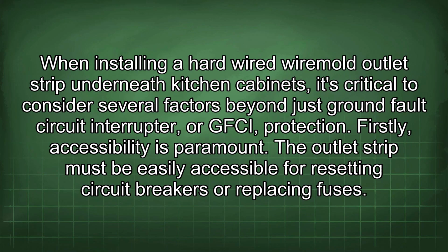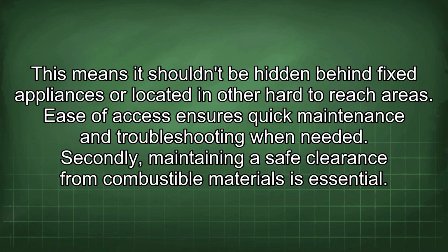When installing a hardwired Wiremold outlet strip underneath kitchen cabinets, it's critical to consider several factors beyond just ground fault circuit interrupter, or GFCI, protection. Firstly, accessibility is paramount. The outlet strip must be easily accessible for resetting circuit breakers or replacing fuses. This means it shouldn't be hidden behind fixed appliances or located in other hard-to-reach areas. Ease of access ensures quick maintenance and troubleshooting when needed.